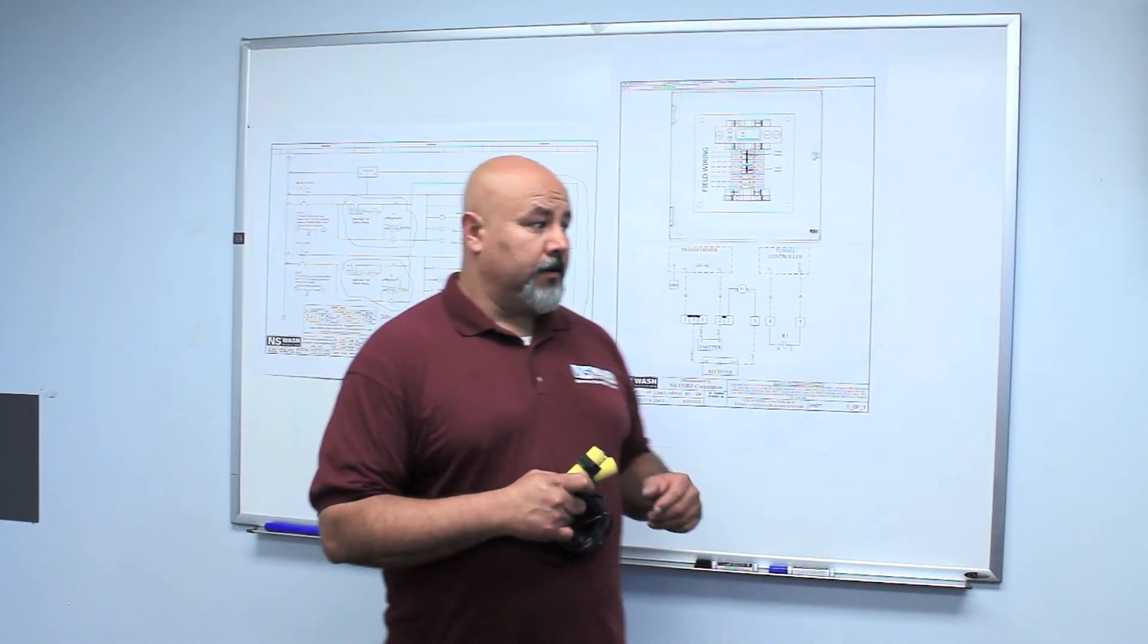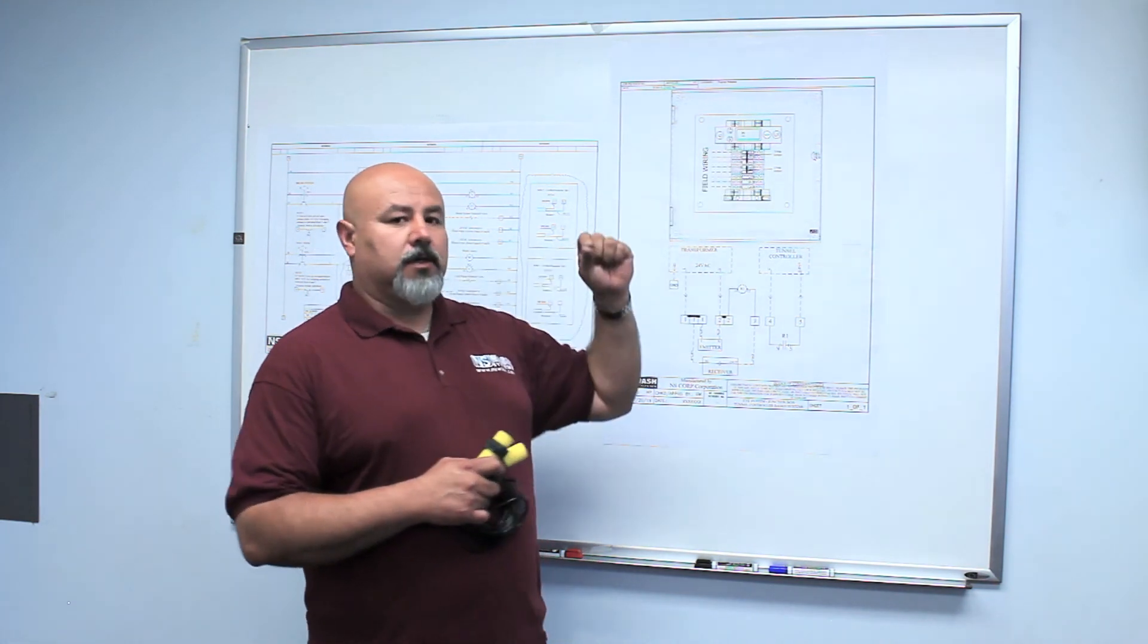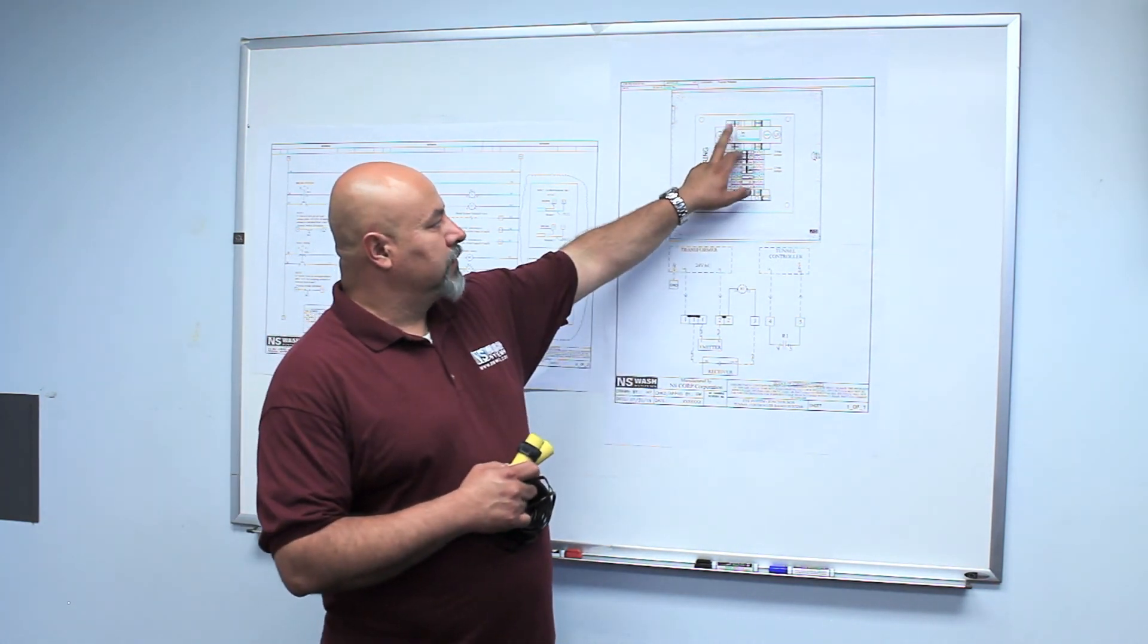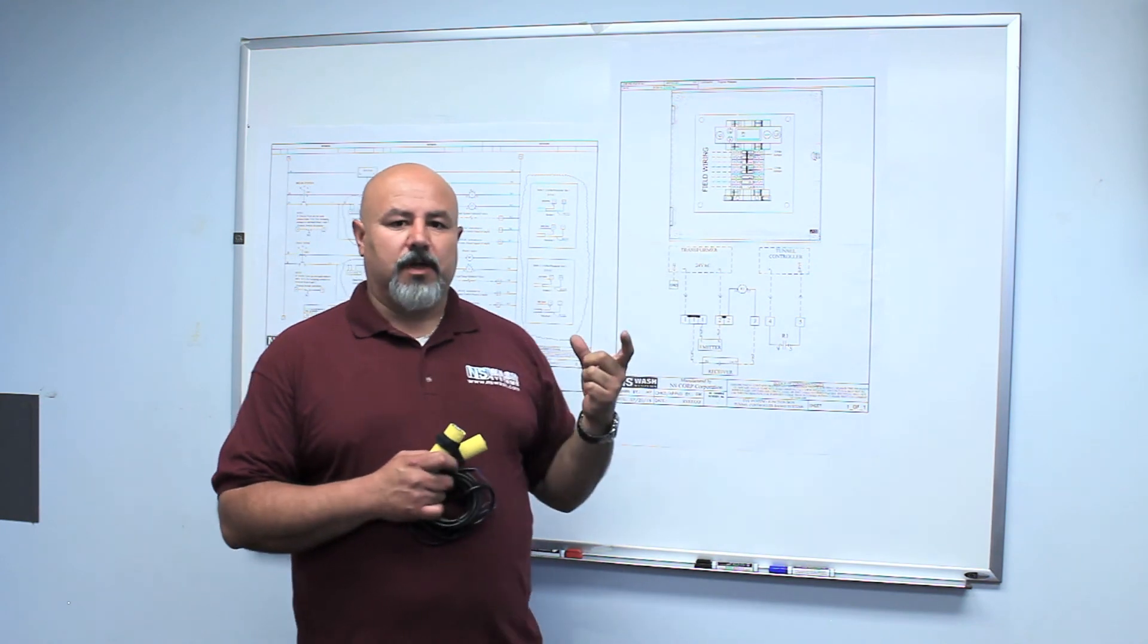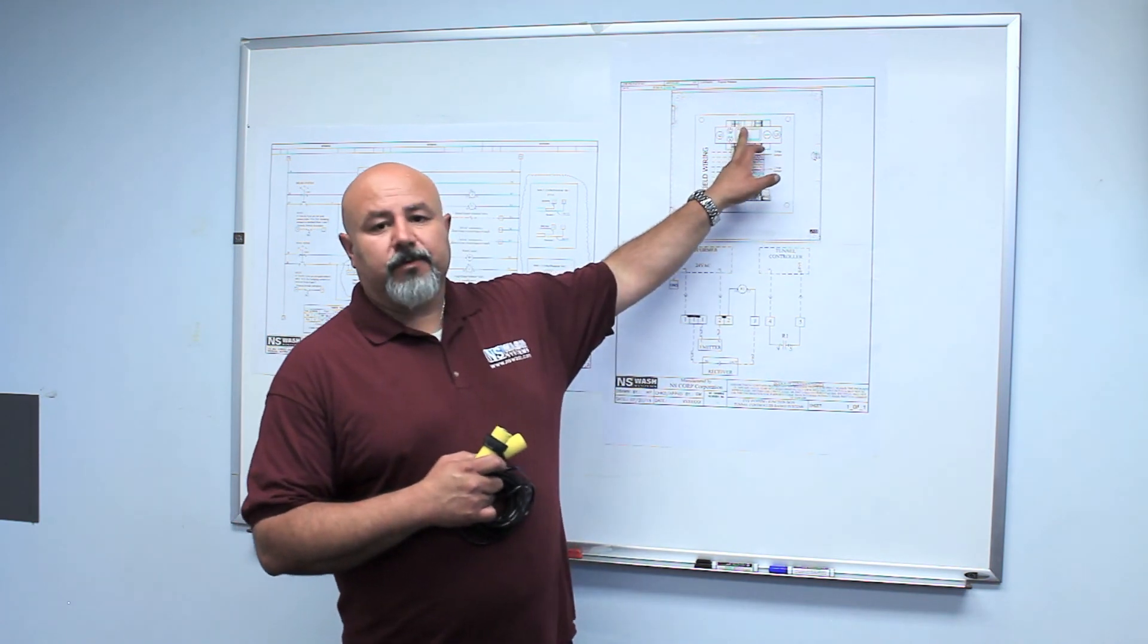The other thing for constant activation would be that in this case, the relay stuck closed. So the two terminals, they melted together, they stuck together. So that's going to be a constant activation. You'd have to replace the relay for that.